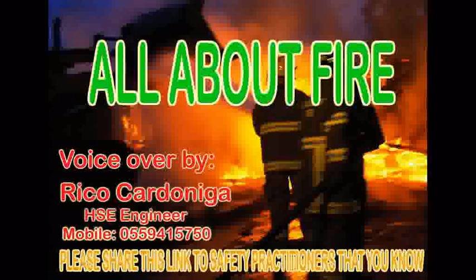Ways of preventing fire: eliminate or reduce the storage of flammable materials, control of ignition sources, control smoking and smoking materials, good housekeeping and preventing accumulation of rubbish, lubrication of machinery to prevent friction, no overloading of electrical systems, regular inspection of electrical systems, ventilation outlets not obstructed, controlling hot work with permits, proper storage of flammable liquids, segregation of incompatible chemicals, security to prevent arson, and regular inspection and supervision.